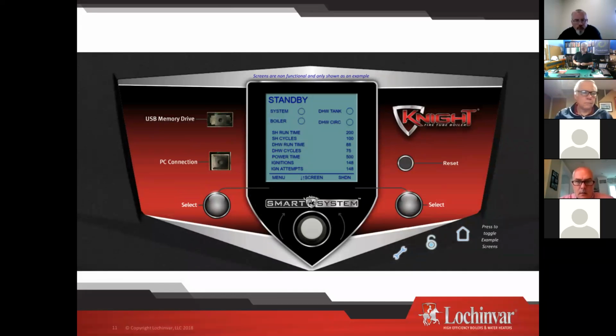I want to talk about cycling of the boiler. We do talk about this in the service class, but this is where you find it, okay? We're looking at runtime and cycles right here. So if you do the math, I've got 100 cycles for 200 hours of runtime. That means that boiler was running 2 hours every time it lit. That's outstanding. In our fire tube boilers, we really want to see no more than 6 cycles an hour. Like to get it down as low as possible. And in our water tube boilers, we want to see no more than 10 cycles an hour. And that really just gets into the longevity of the product plus the efficiency.